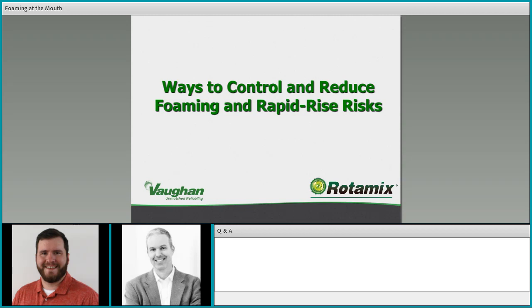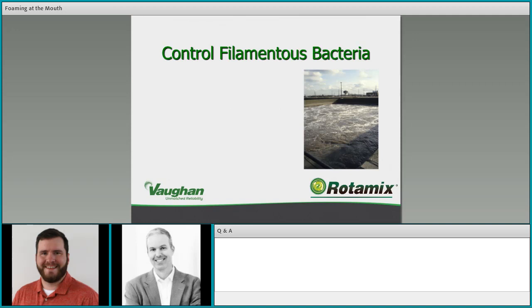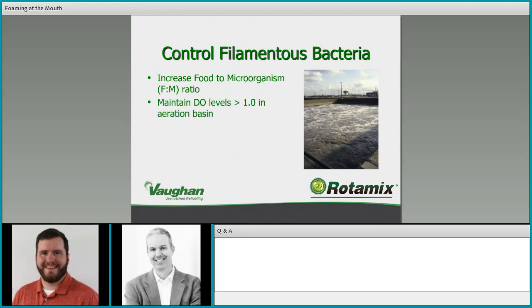Ways to control and reduce foaming and rapid rise risks: controlling filamentous bacteria is number one. If you can take samples from your digester and identify filamentous bacteria, that's a good first step to addressing foaming risk. Increasing the food-to-microorganism ratio in your aeration process can definitely reduce filamentous bacteria — they do not compete well with aerobic bacteria, and maintaining DOs in excess of 1 mg/L, ideally 2–3 mg/L, will allow other bacteria to out-compete them.